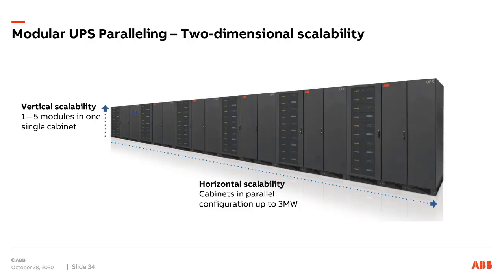And the test technician, it was a test base, so the cable was just pluggable into the feeds and to the load and so on. But just wheeled in the 3rd UPS, plugged it in, and closed the breaker so it was parallel with the first 2, and increased the load from 1 megawatt to 1.5. Never went to bypass, never shut down, never did anything. So that doesn't mean any customer, and I doubt any customer would ever do that in the field, but the unit is designed to do that. So other than that, I guess the key words are the integrated redundancy and the flexibility.